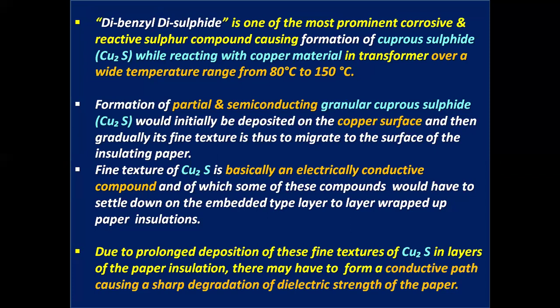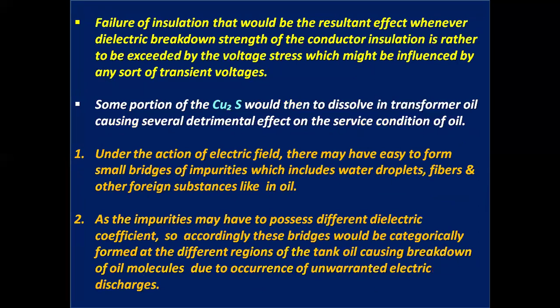causing a sharp degradation of the dielectric strength of the paper. Failure of insulation would be the resultant effect whenever the dielectric breakdown strength of the conductor insulation is exceeded by the voltage stress, which might be influenced by any sort of transient voltages. Some portion of the cuprous sulfide would then dissolve in the transformer oil, causing several detrimental effects on the service condition of the insulating fluid.